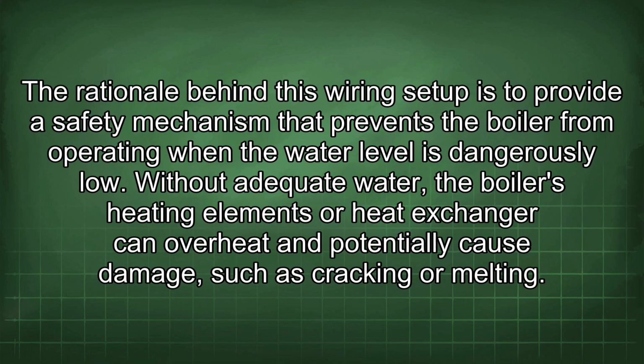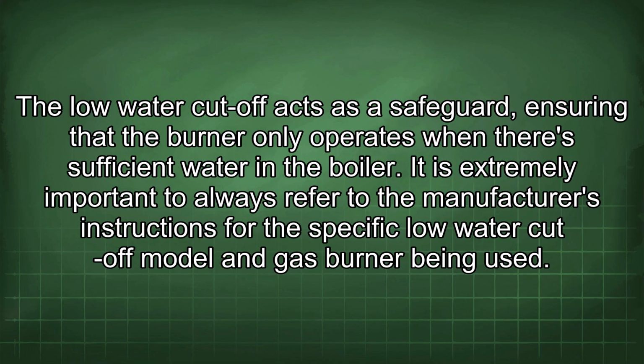The rationale behind this wiring setup is to provide a safety mechanism that prevents the boiler from operating when the water level is dangerously low. Without adequate water, the boiler's heating elements or heat exchanger can overheat and potentially cause damage, such as cracking or melting. The low-water cut-off acts as a safeguard, ensuring that the burner only operates when there's sufficient water in the boiler.